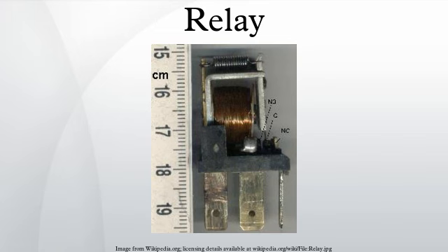If the coil is designed to be energized with alternating current, a small copper shading ring can be crimped to the end of the solenoid, creating a small out-of-phase current which increases the minimum pull on the armature during the AC cycle. A solid-state relay uses a thyristor or other solid-state switching device, activated by the control signal, to switch the controlled load, instead of a solenoid. An optocoupler coupled with a phototransistor can be used to isolate control and controlled circuits.